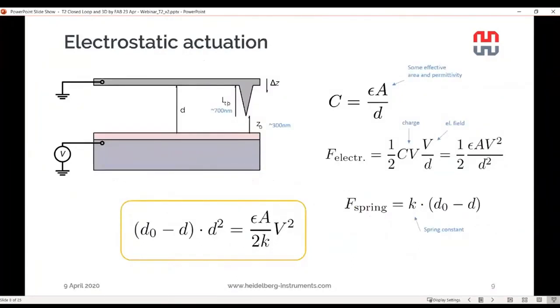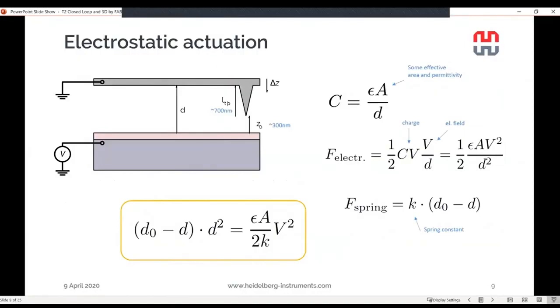So I promised you some physical modeling, and here we go. So when you look at our cantilever structure, it is essentially a capacitor. We have this large platform structure of the cantilever, and then this is a distance away that we call d from the sample surface. We have some height at which the tip is flying over the surface. When we don't apply any force, we call that Z0 here. That's about 300 nanometers. The tip is about 700 nanometers long, so this distance d here is about a micron. And then we can apply a voltage between the two, and then you will get an electrical force that pulls the cantilever towards the surface. And that depends on the voltage squared and some effective electrical permittivity inside this capacitor structure, and obviously the area of the capacitor and the distance here.